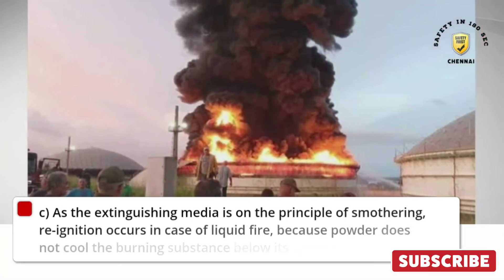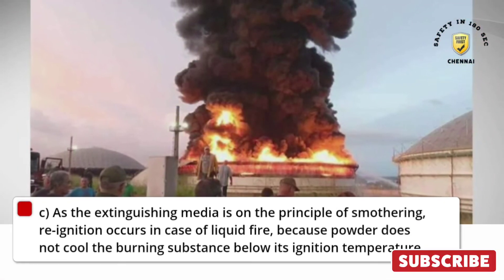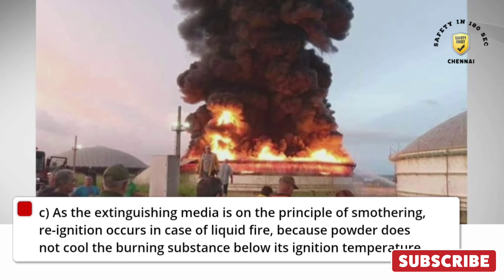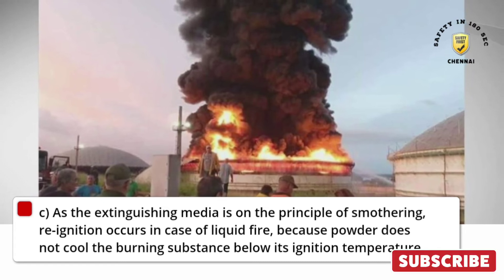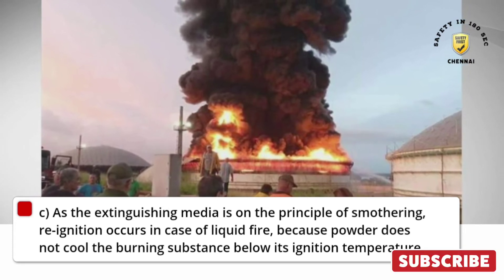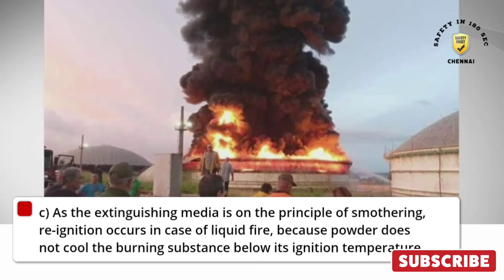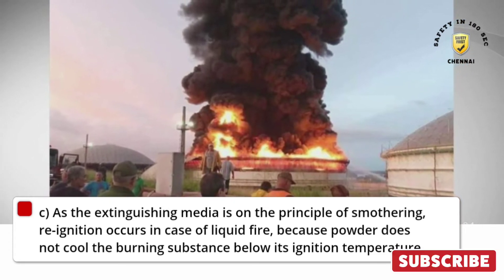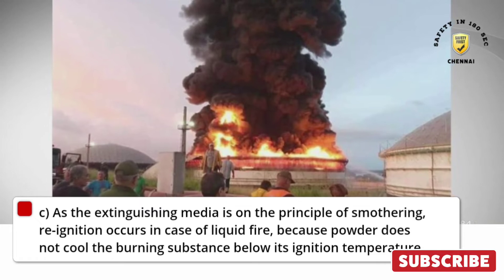As the extinguishing media is on the principle of smothering, reignition occurs in case of liquid fire, because powder does not cool the burning substance below its ignition temperature.